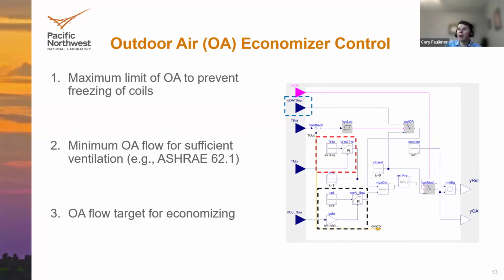And then the third priority is increasing the outdoor airflow to the target for how much is desired from economizing. And so that connects to that other block that we had on the last slide. And so if there is some signal for bringing in more outdoor airflow and you can meet those first two requirements, then you can increase the outdoor airflow to be an energy efficient way to provide cooling to the building.